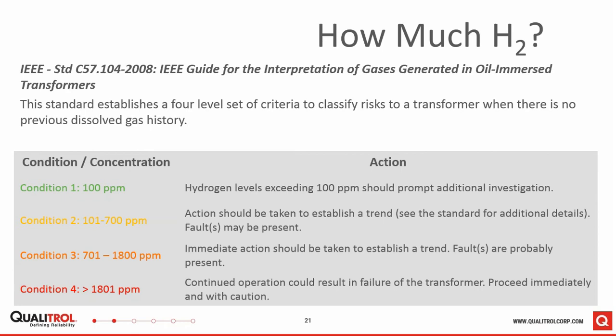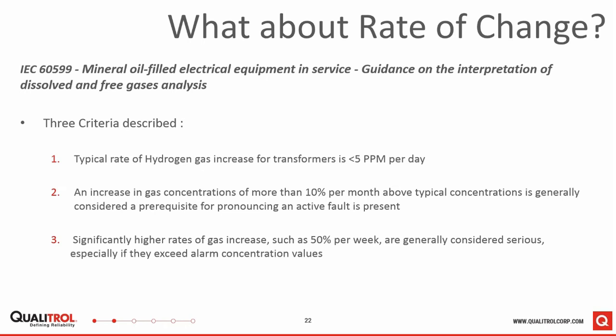So then, we've talked about it already, but what about the rate of change? This is the second parameter that you will get from these online monitors. Again, we can go back to international standards for rules, and we can see that IEC provides some intelligent guidelines. IEC provides 3 criteria. One is that the typical rate of hydrogen gas increase in the transformer should be less than 5 ppm per day. An increase in gas concentration of more than 10%, so percentage rather than ppm, per month above typical concentrations is generally considered a prerequisite for pronouncing an active fault.